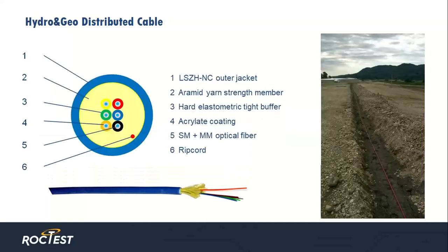Finally, we have the hydro and geo distributed cable. This is again a combined strain and temperature sensor. The cable contains four single-mode fibers and two multi-mode fibers, allowing the sensor to be used both with the DITeS interrogator for distributed strain and with the DITeM DTS interrogator for temperature monitoring. It's possible to discriminate the strain from the temperature and vice versa 100%.